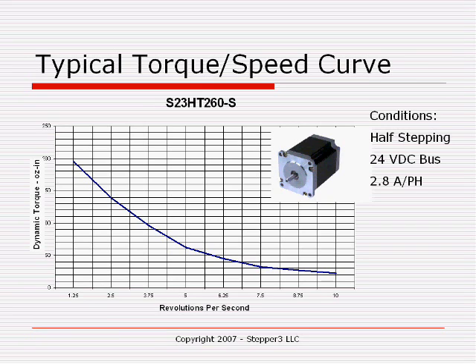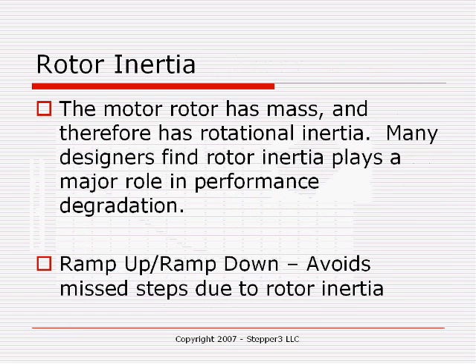For every torque speed curve, the manufacturer will give you the conditions under which that curve was measured, because voltage plays a significant impact, as does the type of driver used. In this case, the curve was done with a half-stepping driver, a 24-volt DC bus voltage, at the rated current of 2.8 amps per phase.